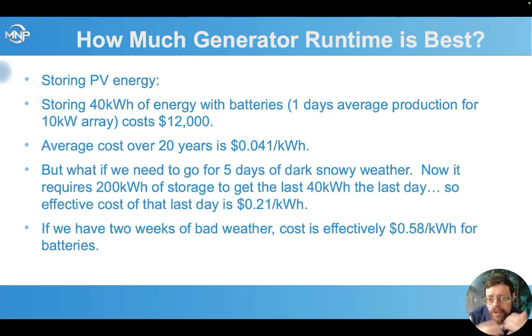Now we've got to have a much larger battery bank, and it's just to get us to that last day of storage. So effectively, the cost during that last day is a lot more. In this case, after 5 days, we're up to 21 cents, and that's our storage cost to reach that 5 days in. If we've got 2 weeks, now we're all the way up into the 60 cents range. So you can see that trying to store energy for long periods starts getting very expensive effectively to get to the end of that long period. That's where it can make sense to, instead of just adding more batteries, switch to running the generator.